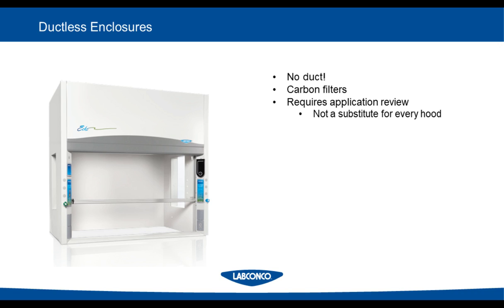There are a lot of benefits that come with a ductless enclosure or ductless fume hood, and one of them would be energy efficiency. As I've stated before, ducted fume hoods will take air out of a building that has been tempered to the comfort level of the lab and exhaust it out of the lab space. Then air has to be supplied into the lab, so untempered air has to be brought into the lab space. All of this takes money, to make sure that the air, the temperature, the humidity, all of it remains constant. With these ductless hoods, no air is exhausted. So that is a benefit in that it doesn't present as big a burden on an HVAC system.